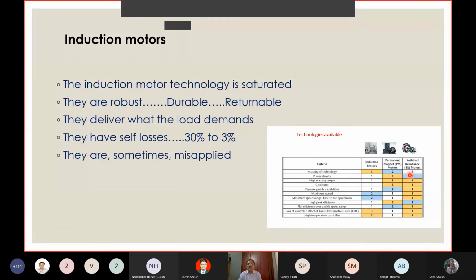These two are new technologies. And in terms of efficiency, as you can see here, high peak efficiency, on a scale of 1 to 3, the highest efficiency is permanent magnet, followed by switched reluctance, and then only induction motors. So induction motors have limitations when it comes to growth in IE standards. They are very good for IE4. Beyond that, they are not going to be suitable.